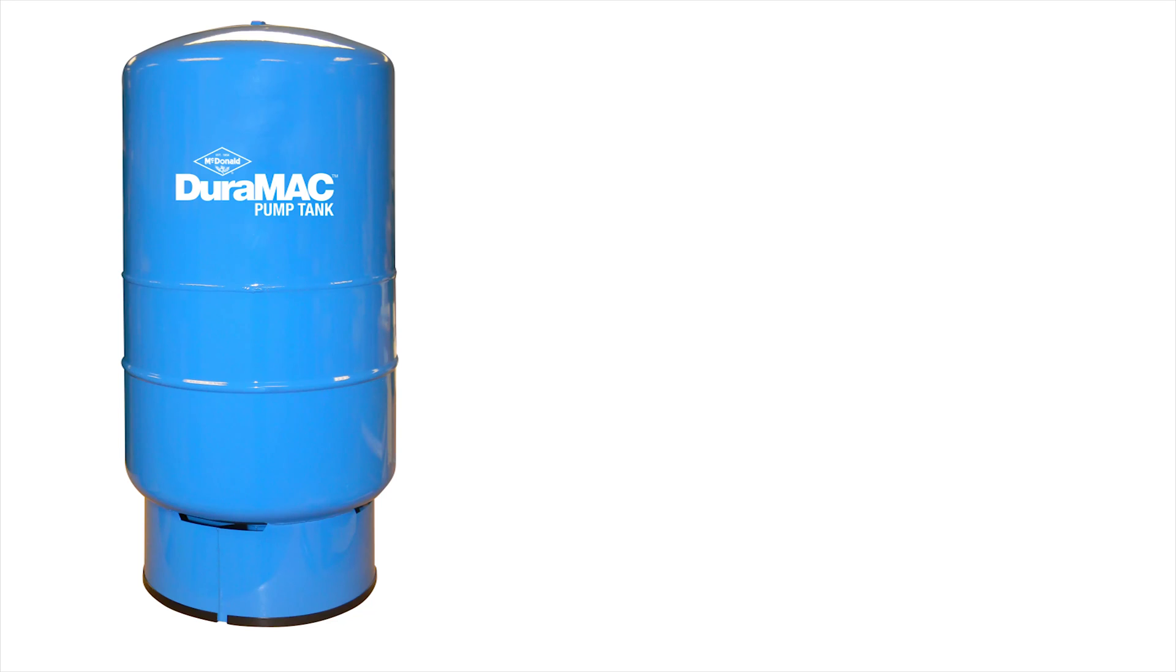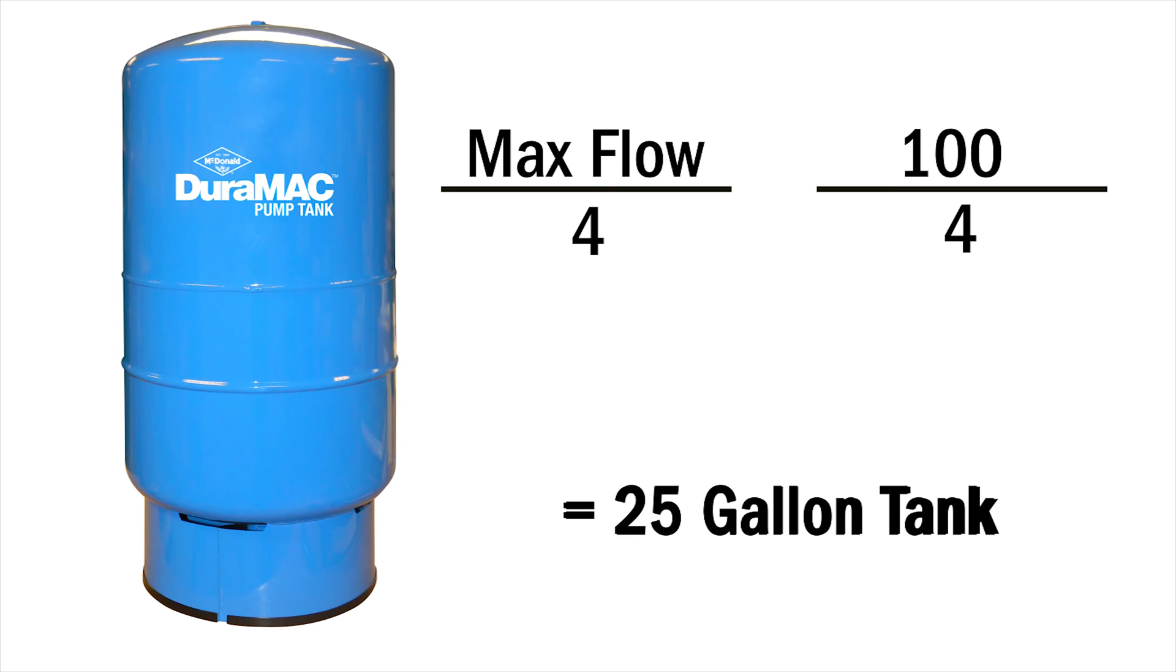All the Duramac boosters require a pressure tank. The size of the tank should be selected by taking the maximum flow of the pump and divide it by 4. For example, if the maximum flow of the pump is 100 gallons a minute, you'll need a 25-gallon pressure tank.